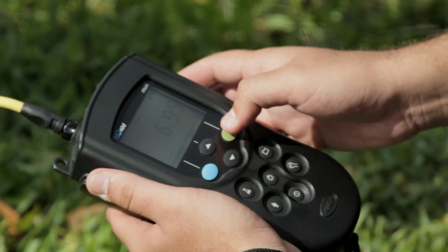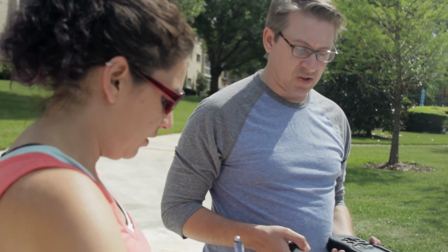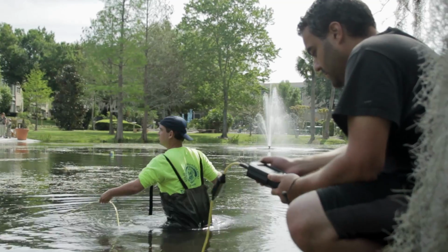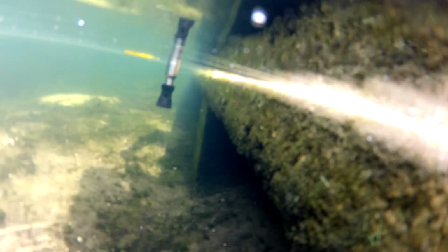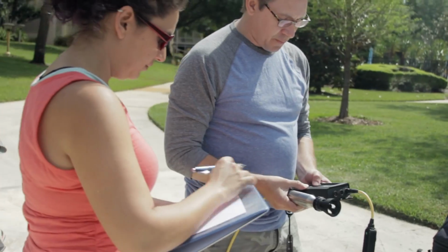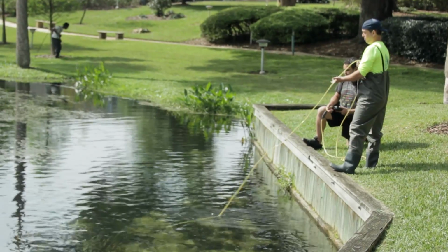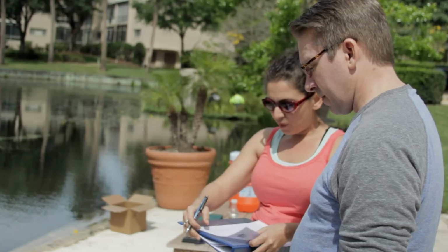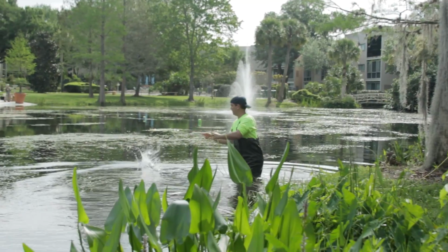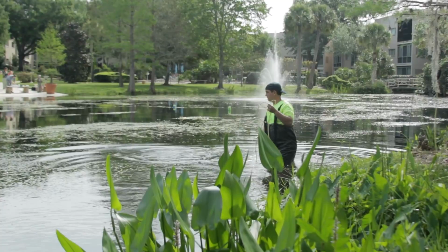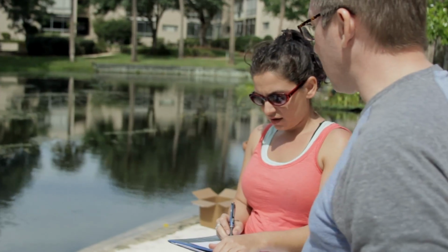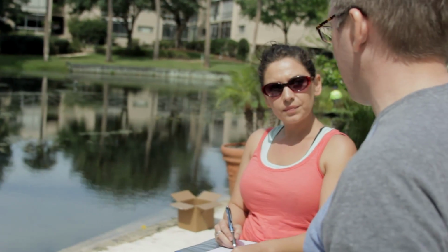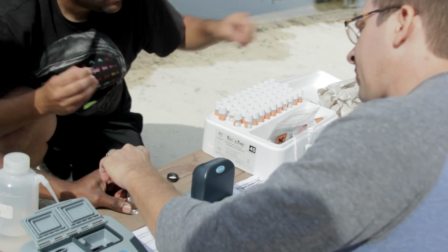So this is what we call our LDO probe. It's a luminescent dissolved oxygen. So this sensor, it detects the amount of oxygen in the water. Let's go through our samples. Location M is at Michael, 6.68. What is an ideal range? Below 2 would be bad. Okay. Below 2. If you get down to like under 0.1 or 0.2, you're going to start killing fish.